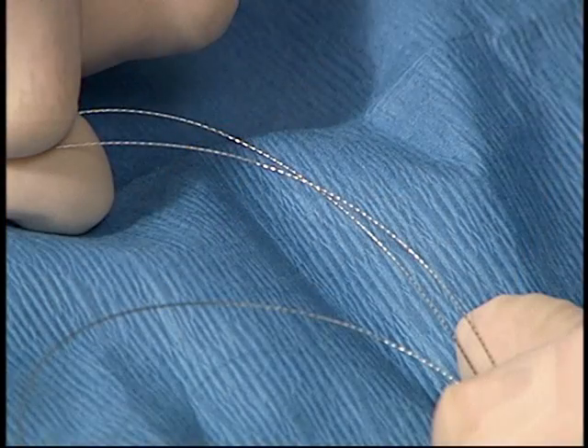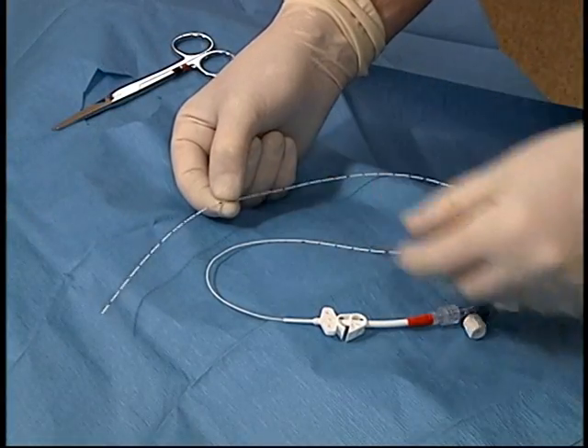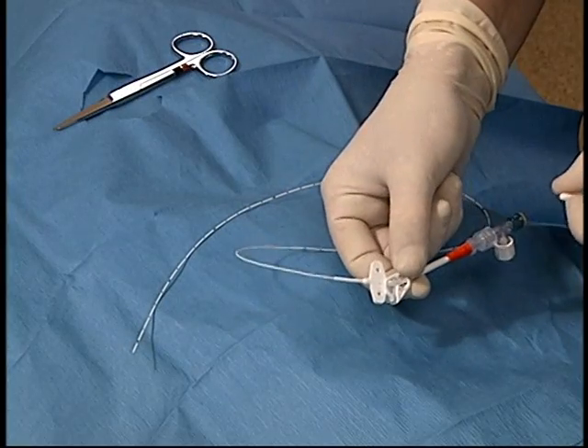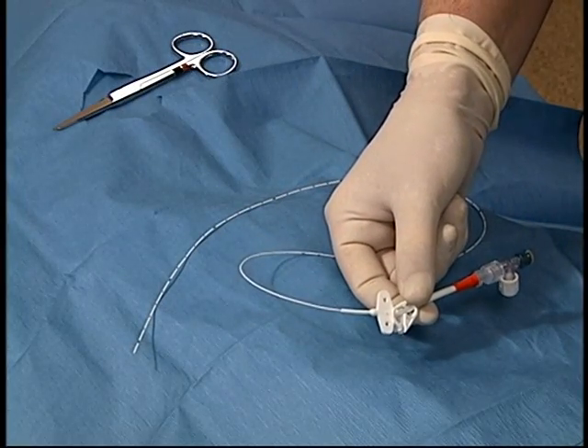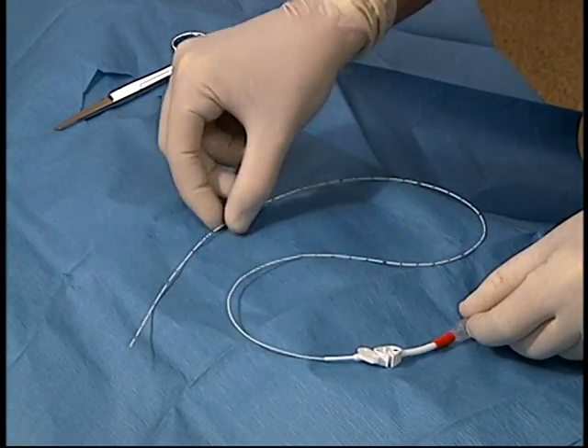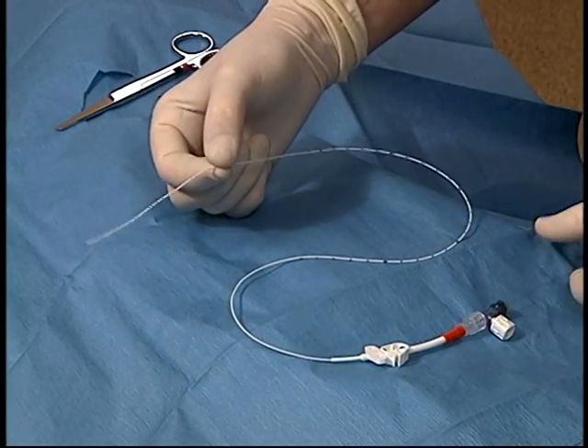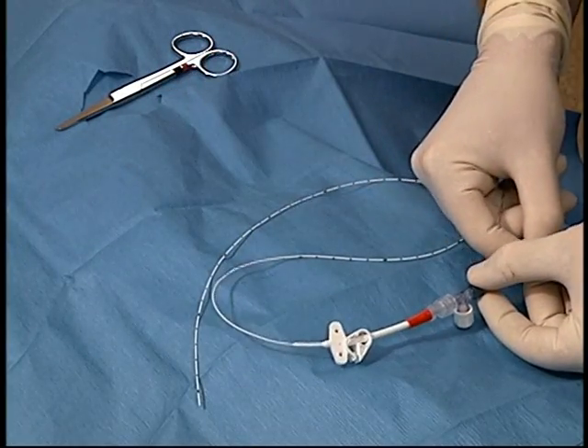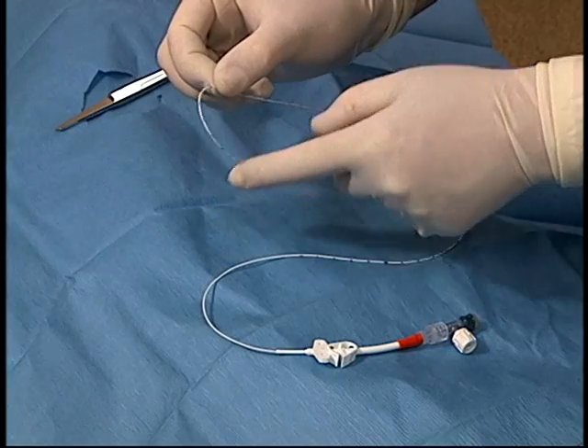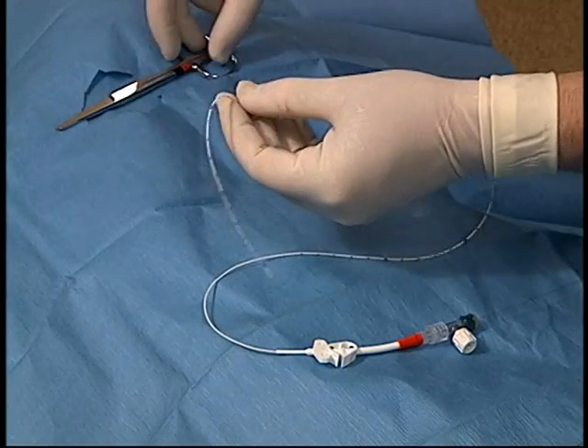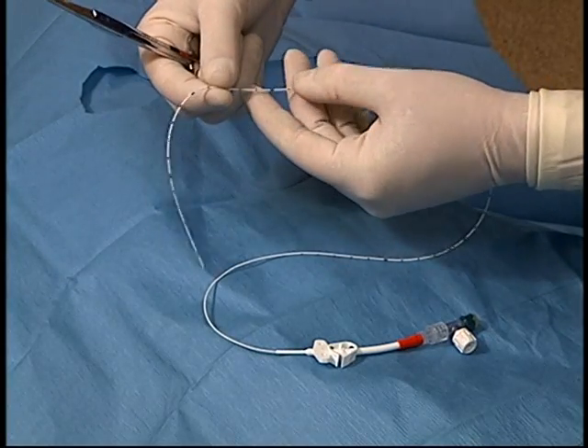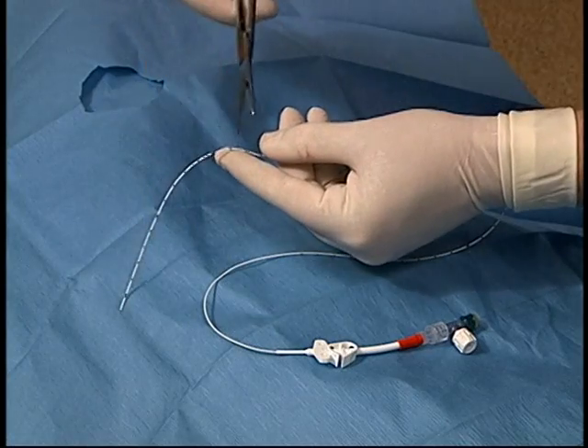The catheter has an inner stylet, which is a woven wire which provides rigidity for placement. These catheters can be cut if they are too long. The inner wire, which cannot be cut because of its woven nature, must be retracted until the catheter is of a suitable length, and then the end of the catheter is cut. It's extremely important to remember not to cut the wire.